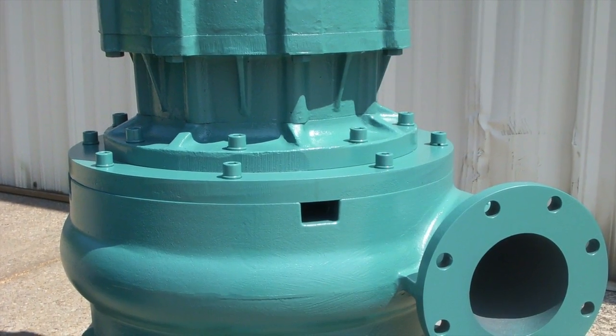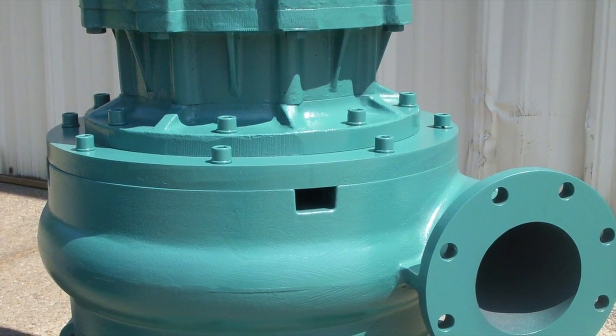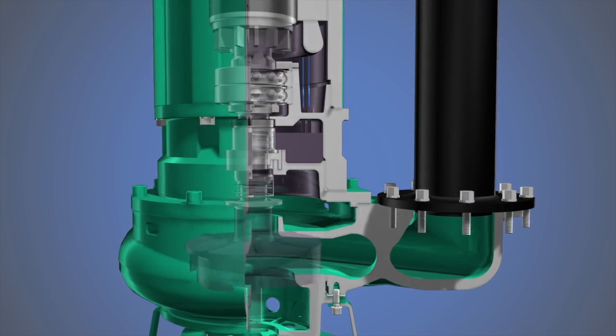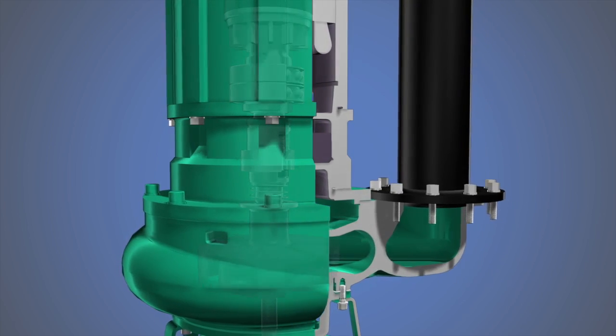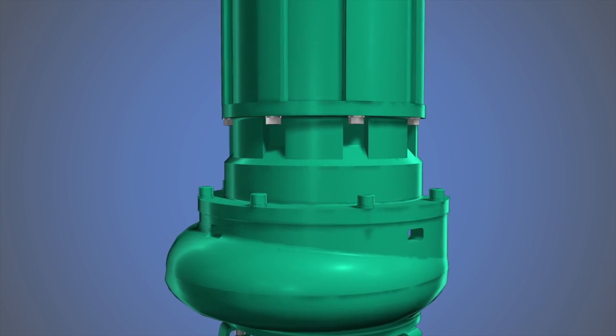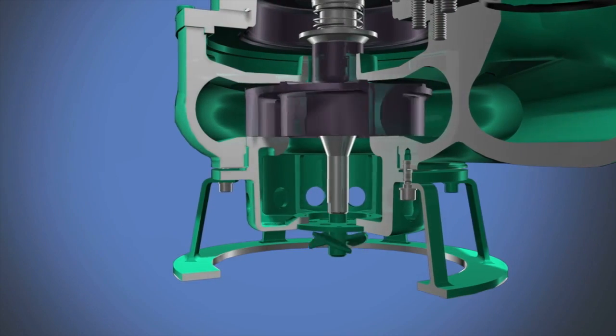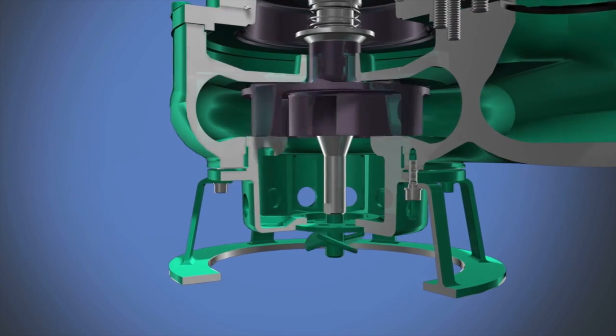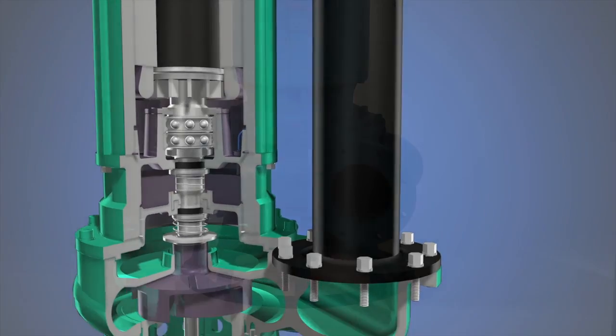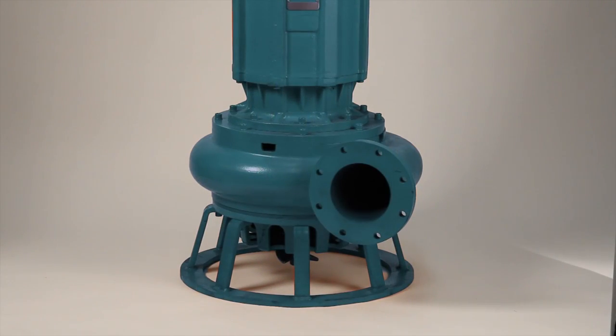Our design has four circumferential casing vents which connect the mechanical seal chamber to the sump, ensuring that the motor mechanical seal arrangement is never exposed to pressures in excess of submergence depth times slurry density. Our unique dual seal chamber flinger arrangement works in concert to provide continuous low-pressure fluid circulation, thus flushing and preventing solids buildup in the mechanical seal chamber.